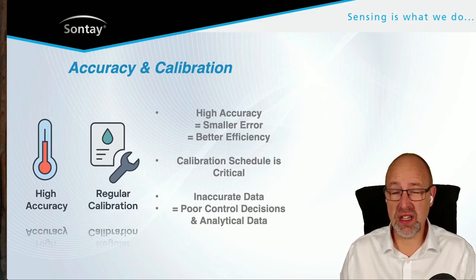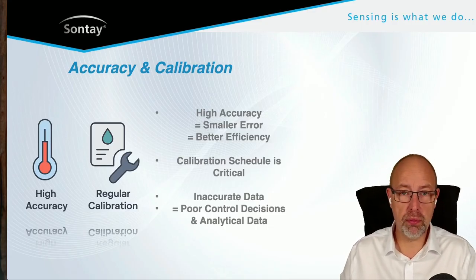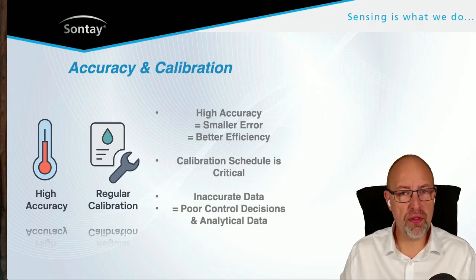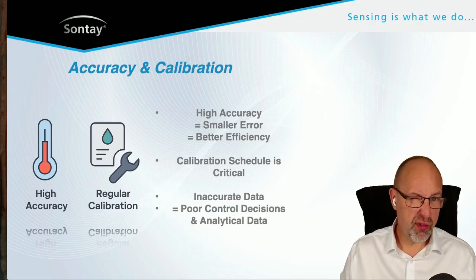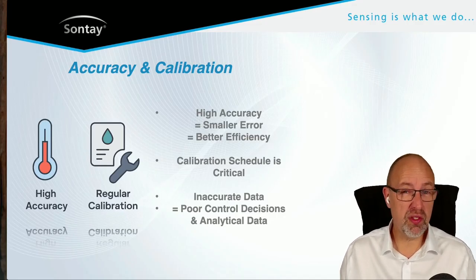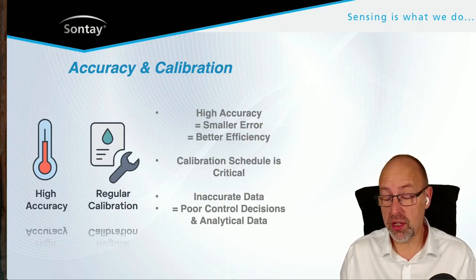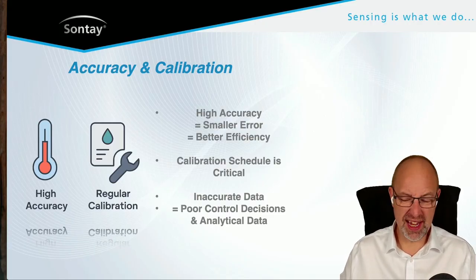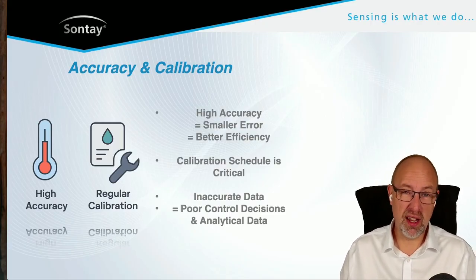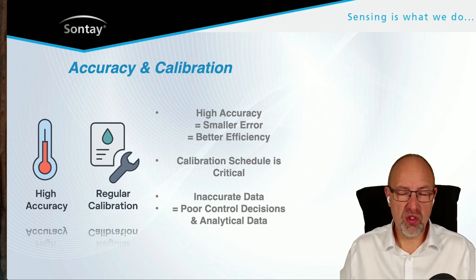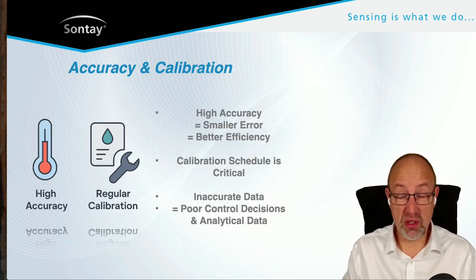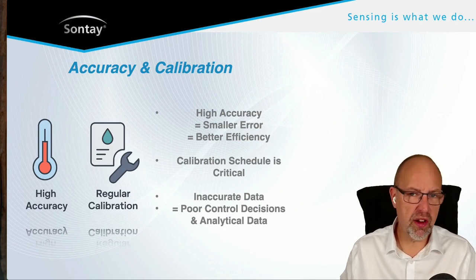But having that schedule to make sure that the sensors are still accurate is very important. And different sensors will require different levels of calibration. For example, a simple thermistor will probably only need checking once a year. It's really unlikely it's actually going to need any adjustments to it, because it's just a simple semiconductor, a thermal resistor. There's not a lot can change. Sometimes they fluctuate, but there's very little change.